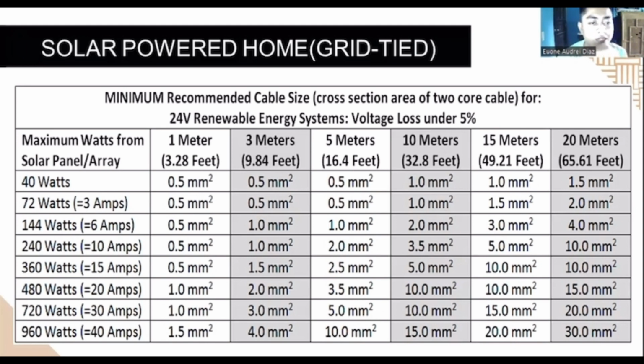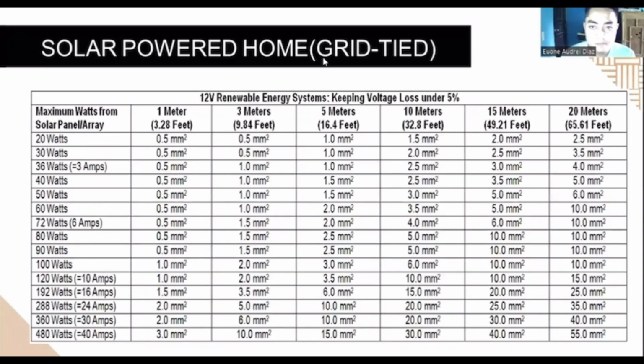For example, sa maximum watts from the solar panel array, pumapasok dito yung 40 watts. Tapos makukuha niyo sa 1 meter or the 3.28 feet is 0.5 millimeters squared. And susunod 0.5 millimeters squared. Hanggang sa 10 meters makukuha niya is 1.0 mm squared, and the 1.0 mm squared hanggang sa 20 meters makukuha niya is 1.5 mm squared. Ito, parang ganun lang din yung example niya.